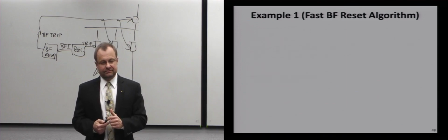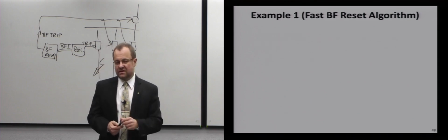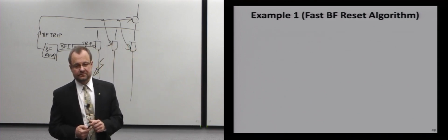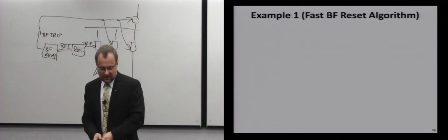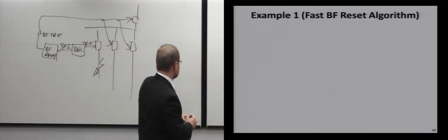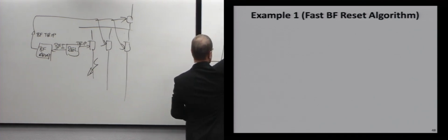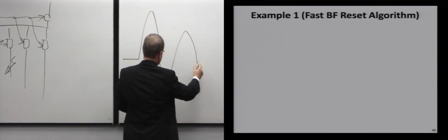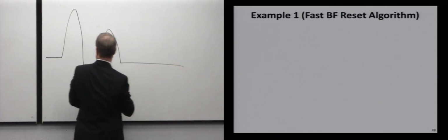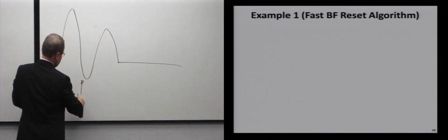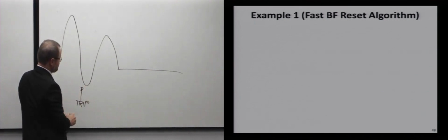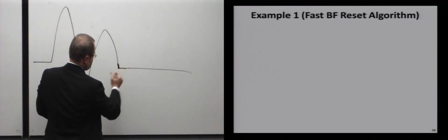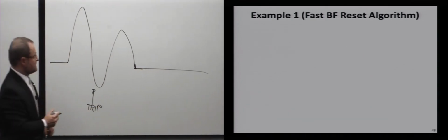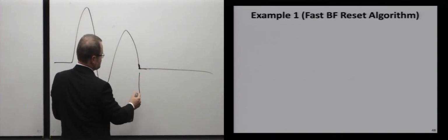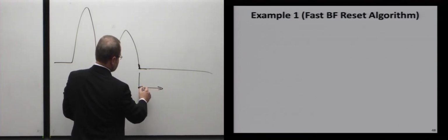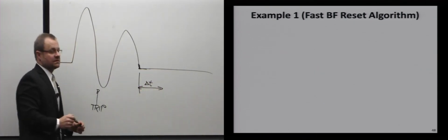3 to 4 seconds. From the moment the current is gone, 3 to 4 seconds. So, if you look at the breaker current, assume that we have a fault, right? So there is a fault current, maybe it's offset. We have a very fast breaker, it interrupted here. So maybe the relay tripped here, and we got a fast breaker at the 0 crossing, it interrupted, right? So this is the time that the current is gone. So how much time here do you think we need to realize that the current is gone?